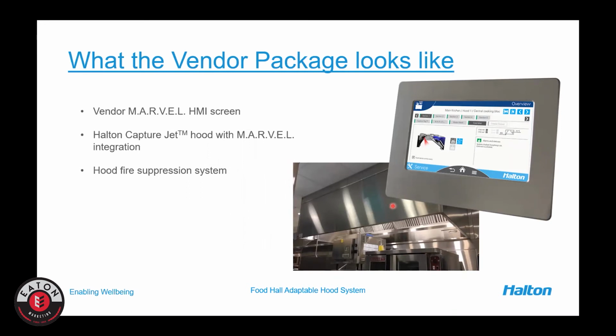You would have the M.A.R.V.E.L controller. There would typically be one for each vendor. And then there would be a master PLC for all the hoods tied to a specific system. And the fire suppression would be another consideration, especially if we are looking to design for flexibility. So we could certainly design for an overlapping type of system that allows us the greatest flexibility in terms of moving appliances in and out over time and changing that equipment layout.